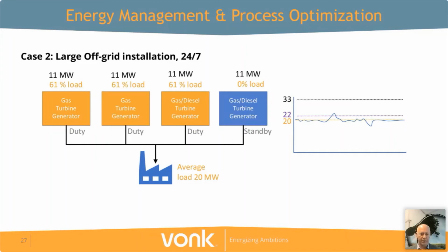It's not an ideal situation. Okay, your load is above the 40% that the turbine should run on, but it's not ideal. And the higher the load is, the more the efficiency will increase. So how can this situation be improved? This is the peak that you want to take care of, and this can be done by introducing again a battery energy storage system.